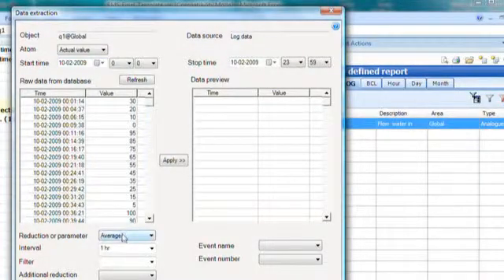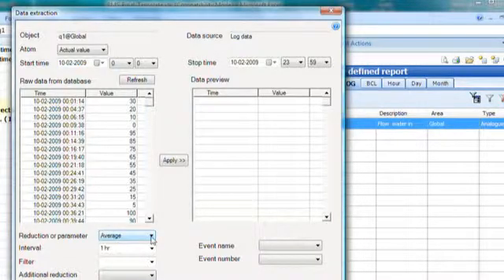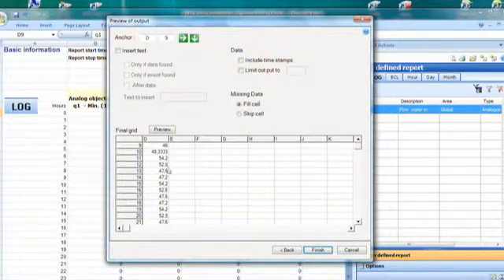On the 10th of February, I have a number of data as you can see here — we simply see the raw data from the database. These are the log values from the IGSS log files. I need to create a calculation on this object. I have selected to calculate the average of all these values in the database, and I want an average for every hour. When I click Apply, I can see the actual values that will end up in my report. And as you can see, 46 is the first value — that was the one I was manipulating. I click the Next button, and I can see that the anchor point is D9.